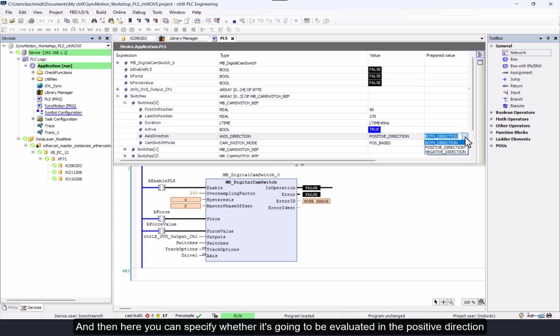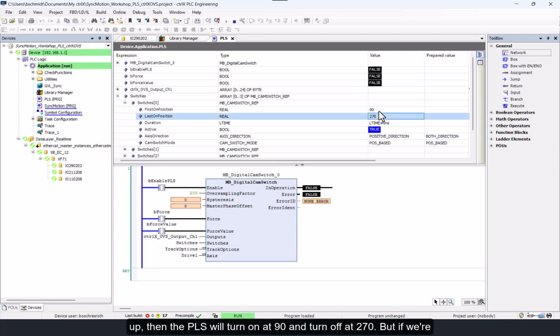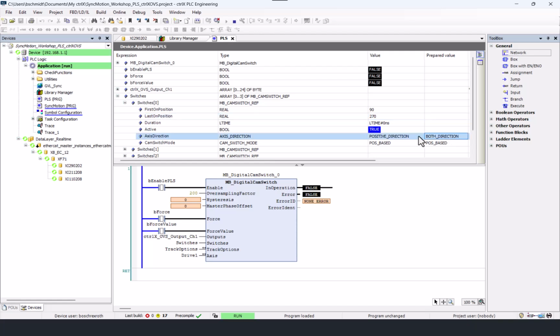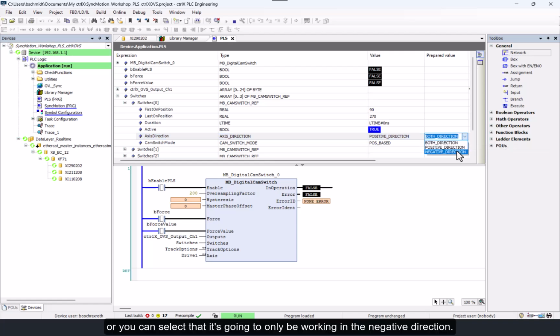And then here you can specify whether it's going to be evaluated in the positive direction, in the negative direction, or both directions. So with this positive direction setting, it means that if the position is moving in the positive direction, in other words counting up, then the PLS will turn on at 90 and turn off at 270. But if we're going in the negative direction, so counting down, the output would not turn on during this range. But if you want it to be active in both directions, you can select that here. Or you can select that it's going to only be working in the negative direction.